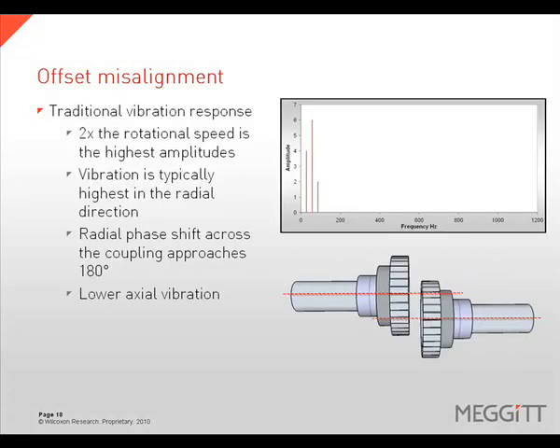Offset misalignment has traditionally been characterized as producing a vibration response at 2x rotational speed, typically highest in the radial direction. With vertical offset, the highest amplitude of 2x vibration is expected in the vertical direction; with horizontal offset, the highest amplitude is expected in the horizontal direction. However, a combination of the two types will create a vibration that is not necessarily purely directional in one measurement plane or the other.